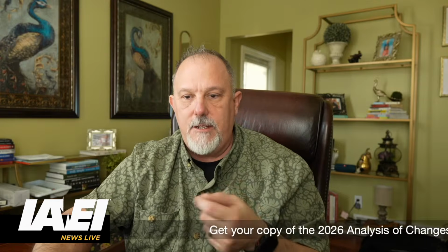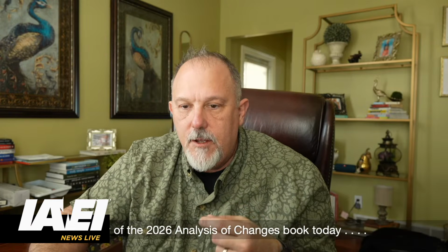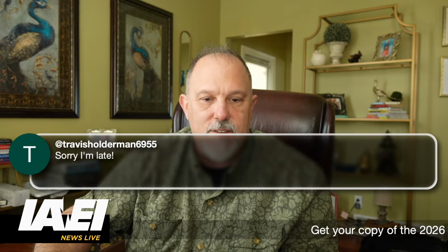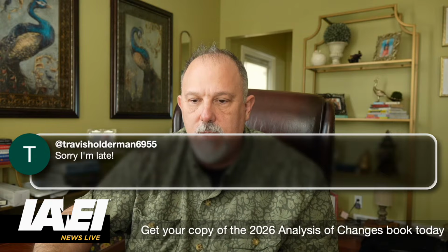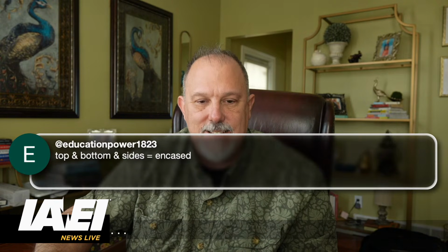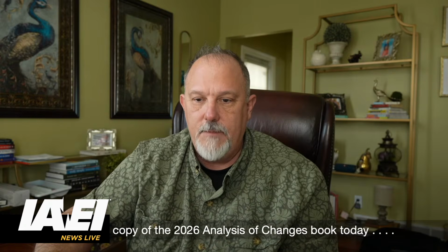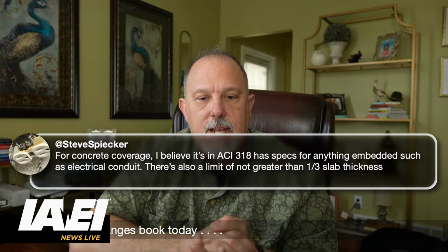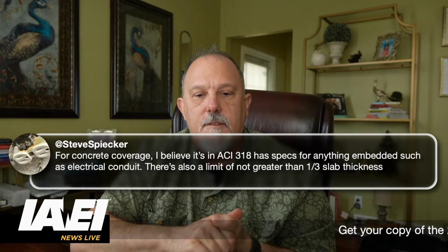Let's take a look at the notes. Wow. I would say on 2 inches on either side, 2 inches, 6, we already talked about that. Hey, Travis Holderman, it's okay. Encased means encircled. Top and bottom equals, and sides, encased. I would say 2-inch conduits would need 4 inches, hence the need for clarity. Steve says, for concrete coverage, I believe it's ACI 318 that has specs for anything embedded such as electrical conduit. There's also a limit of not greater than 1/3 slab thickness. Ooh, interesting.